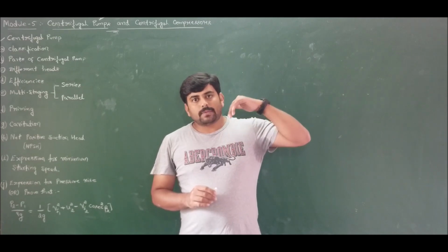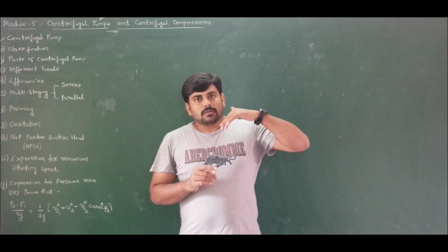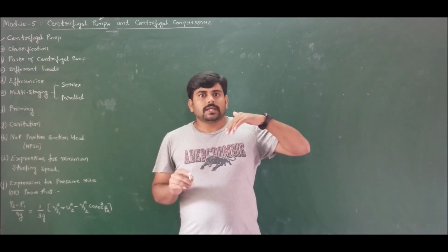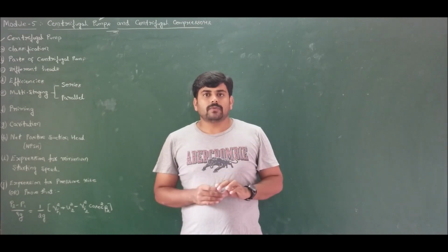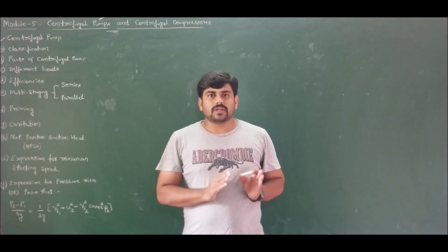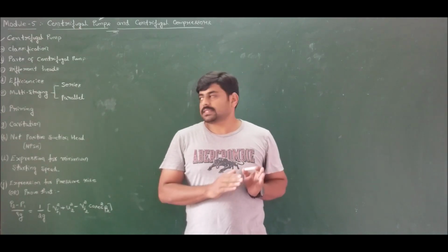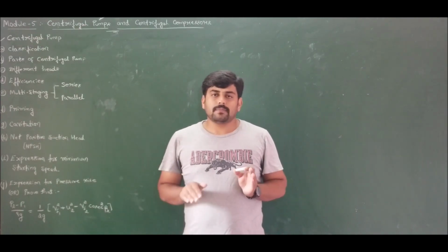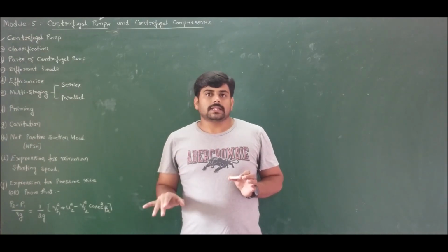We should fill the delivery pipe completely with water manually, and move this air gap out of the impeller section where the pressure rise takes place. Then only will the pump start once again. This phenomenon of getting rid of air blocks inside the centrifugal pump is termed priming. Priming in a centrifugal pump is done to remove the air gaps or air blockages in the working line.